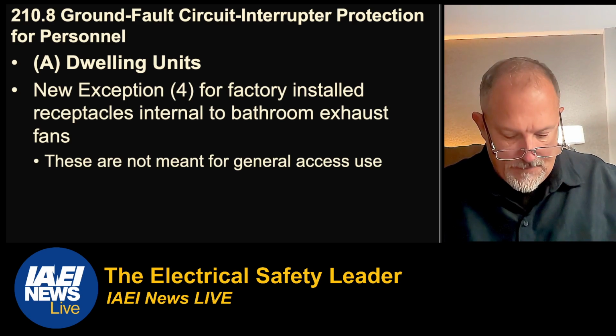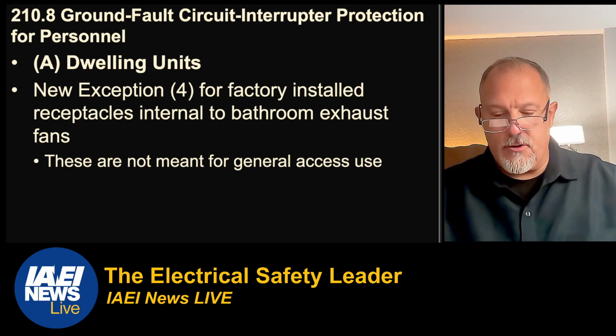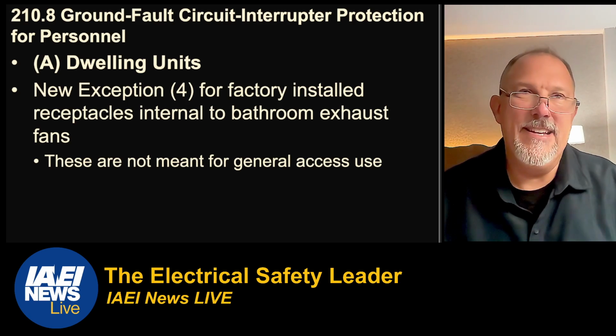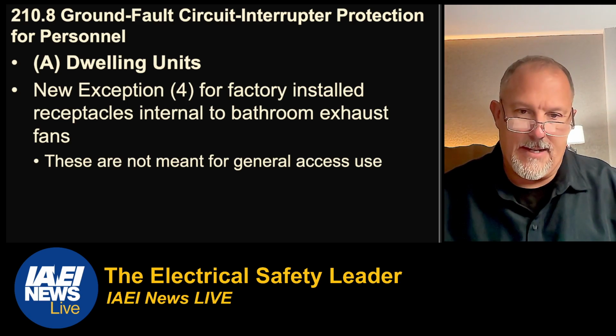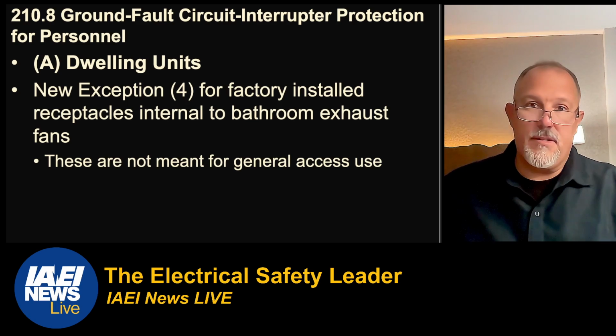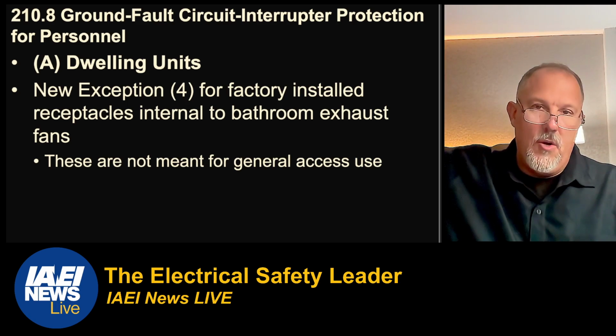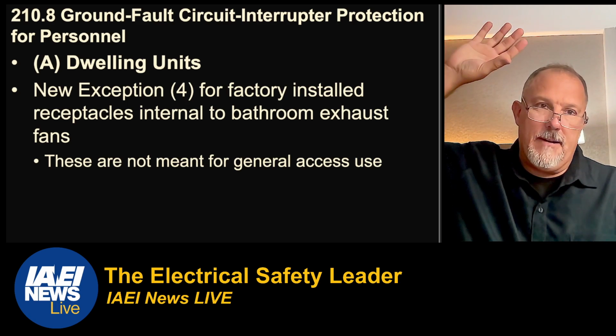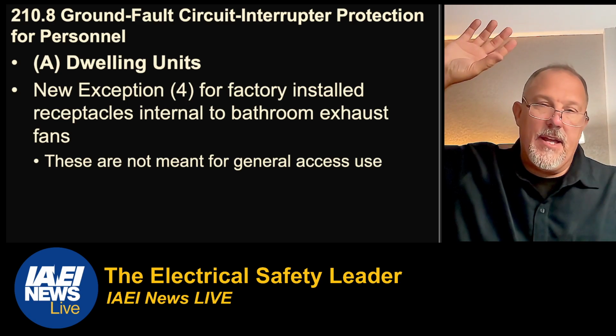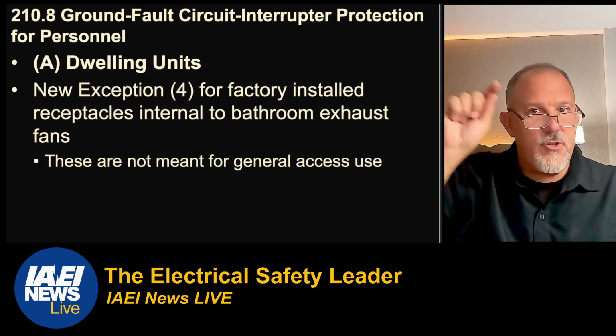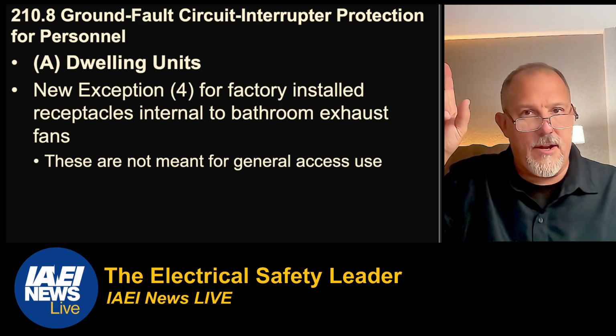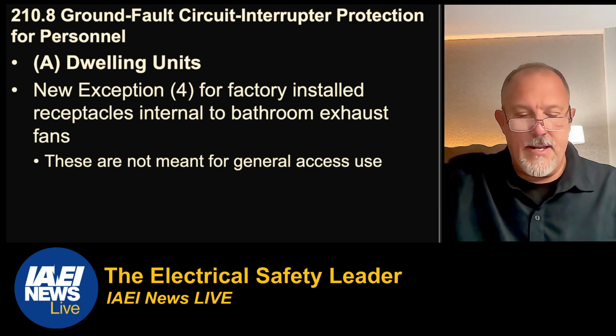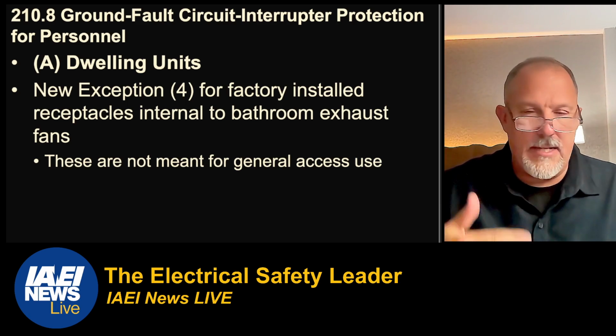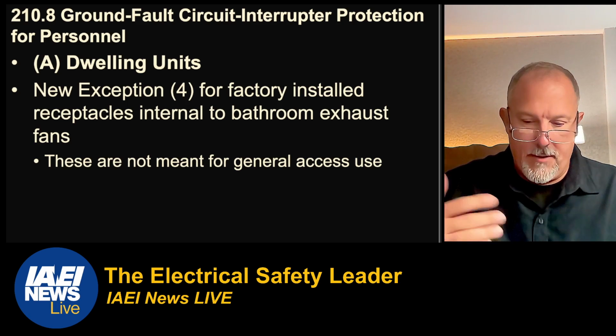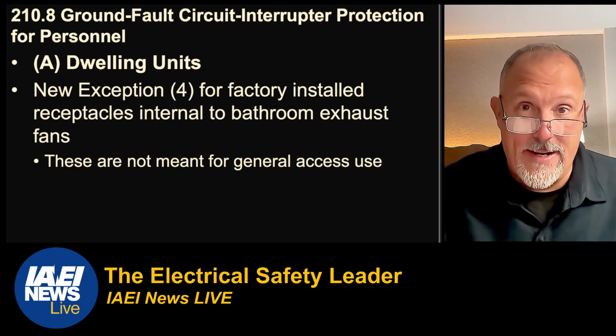There was a new exception for factory installed receptacles that are not readily accessible. Now, this one here, I think they're talking about those fans, like in the bathroom, where you have the fan that does your exhaust. If you take the covers off, there's a little two-prong receptacle in there that's meant for plugging in that fan. That doesn't need to be GFCI protected, and apparently somebody was requiring it.